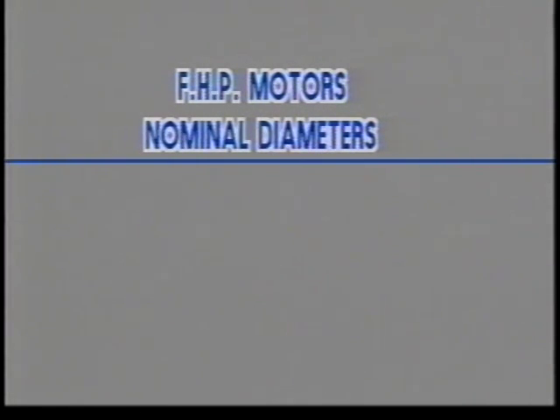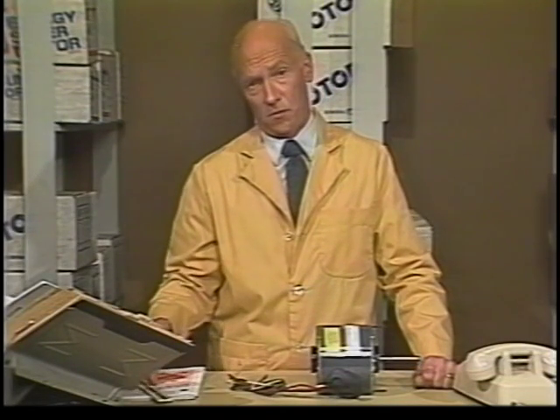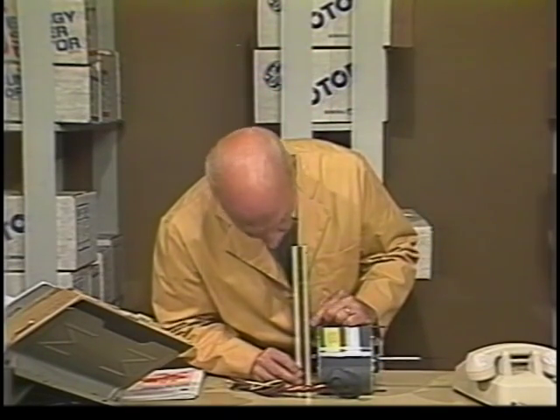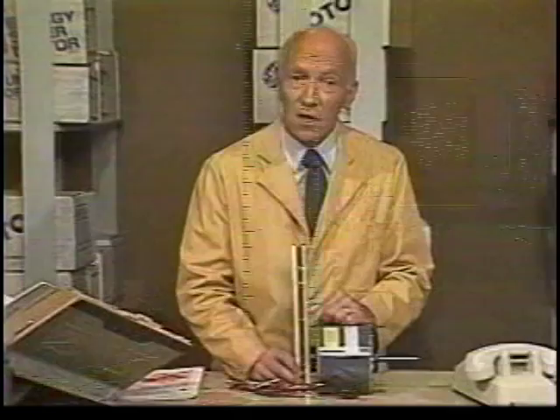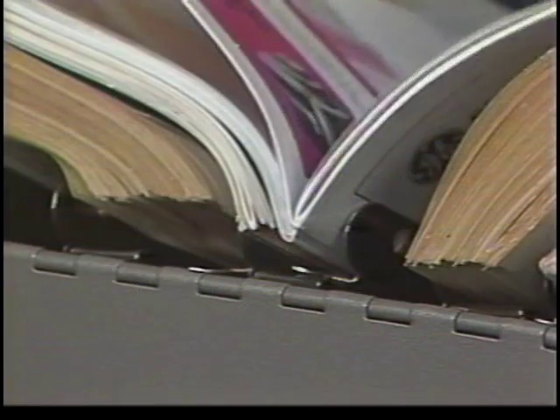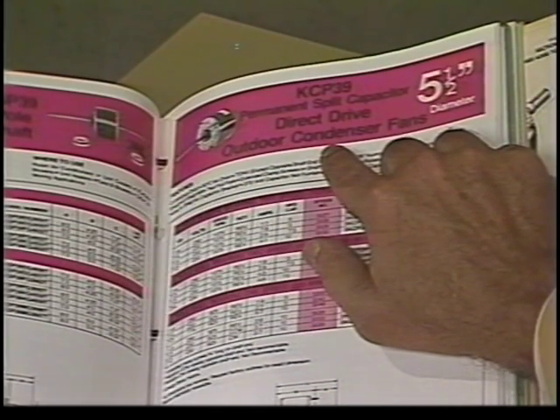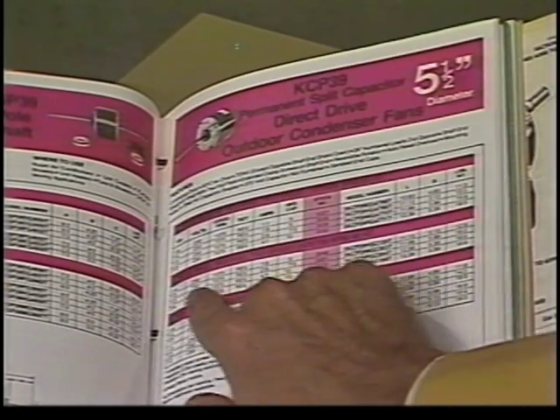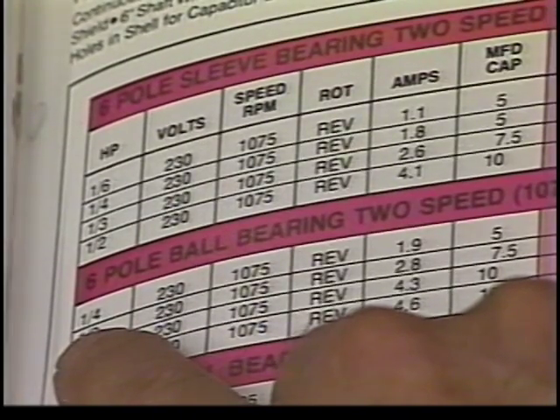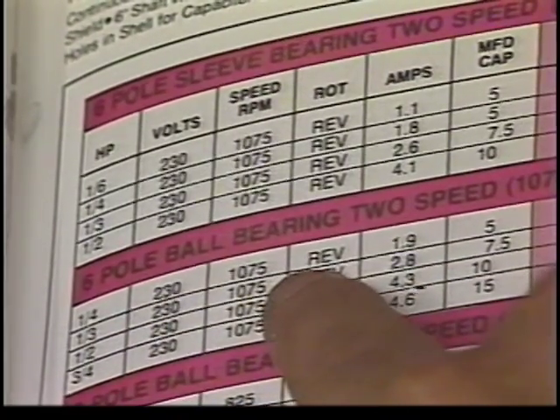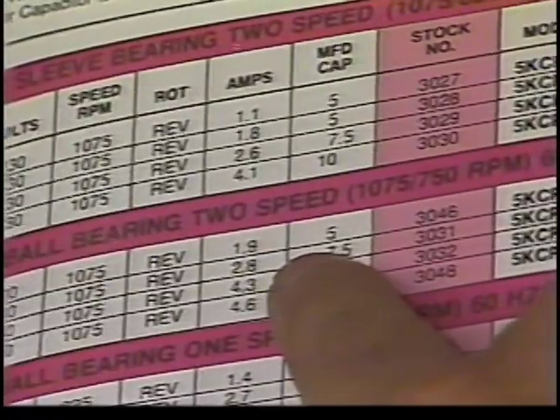It's always wise to double-check the specifications of the original model against those listed for the replacement stock number. The specs for the replacement model are also available in most replacement guides, listed by motor diameter. Most FHP motors come in four nominal diameters: three and a half, four, five, and five and a half inches. If you're not sure, go ahead and measure — if it's three and three-eighths, call it three and a half. For our five-and-a-half-inch motor, we turn to that section. Knowing the application is an outdoor condenser fan, we locate our replacement stock number 3046, which verifies the proper specs for horsepower, voltage, RPM, rotation, amperage, and capacitor rating as compared to the nameplate data on the failed original motor.